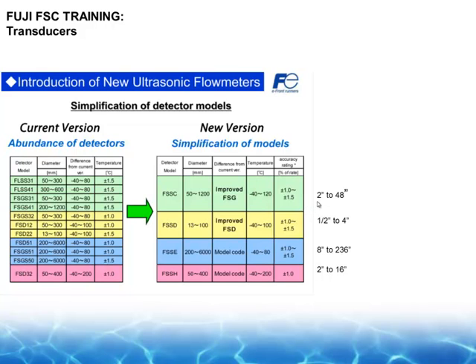It's ideal for 2 to 48 inches, and in some cases we've gone up to 60 inches with this device in the Z configuration. The standard transducer, the FSD-22 2 megahertz, has been around forever. It still works in a half to 4 inches. Its new part number is FSSD. So these are the two workhorses for the Fuji Portaflow-C.